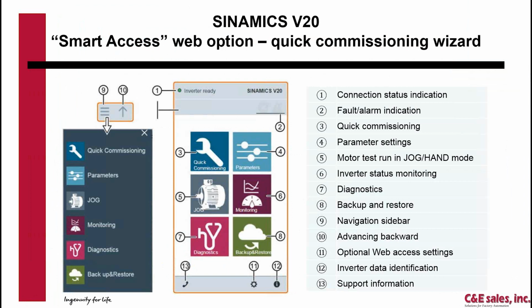Number three is quick commissioning. Quick commissioning is where you're going to come in and set up the drive initially, motor parameters and the basic parameters in the drive. Number four, there's parameters list that shows you the full parameters of the drive that you can get access to and look at or change, modify. Jog's going to be able to put it in a manual control mode from the software. You can get control from the software for the drive and run the motor.